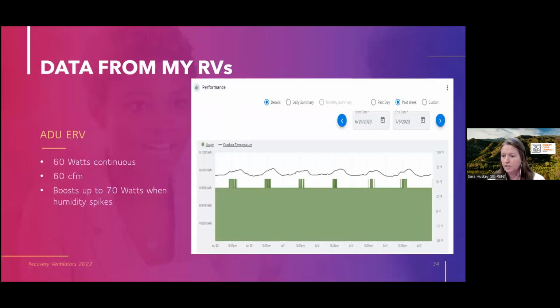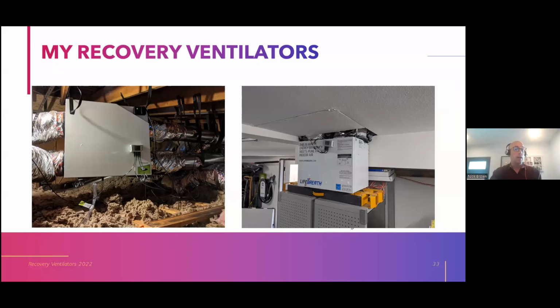And Nick, there was a question that came in asking about accessibility. It says Title 24 compliant software has a checkbox that requires all supply filters, outside air inlets, and ERV recovery core to be accessible. And Mark is asking if this is pretty typical. Yeah, and absolutely critical. So I have to climb up in this attic and change the filters and check to make sure everything's working right and clean out the recovery core. That's not ideal. If I were designing a new home with a recovery ventilator, I'd put it down in a laundry room or a closet or a garage where I could freely access it.